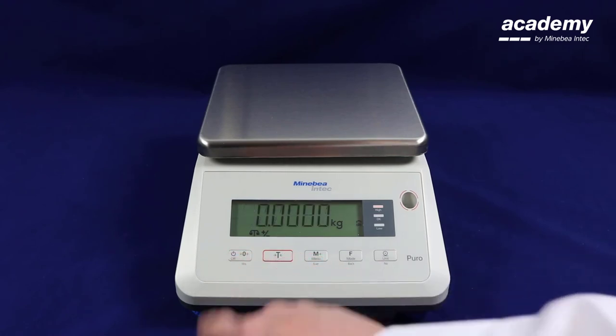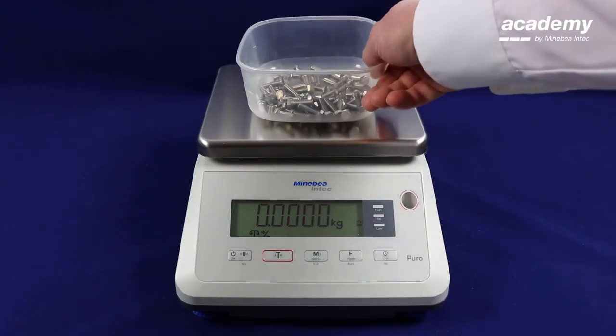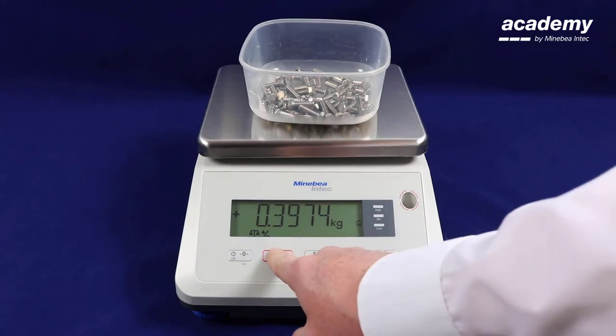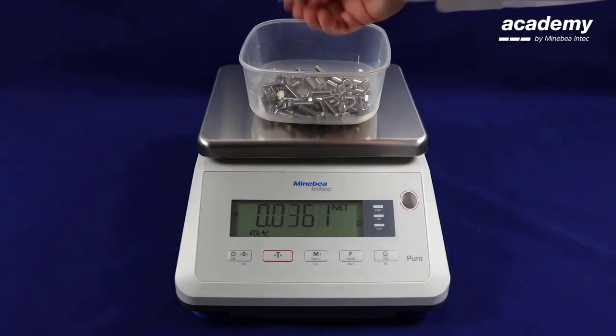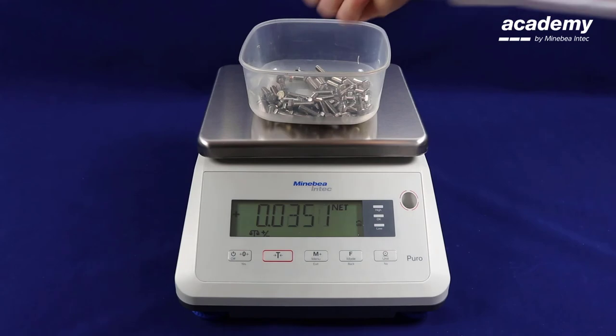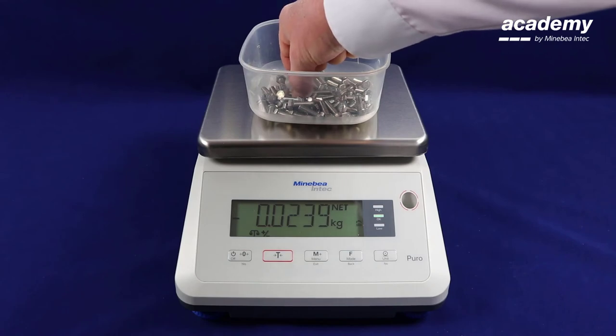Now the application is running. Place your complete product on the scale. Press tare. Start removing pieces of the product until the green light is shown. This is a demonstration of subtractive check weighing. If you take out too many products the red light will show.